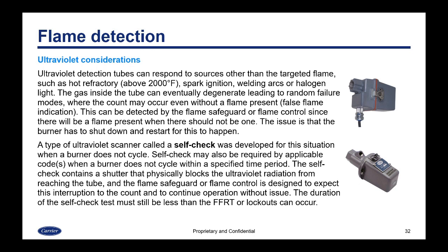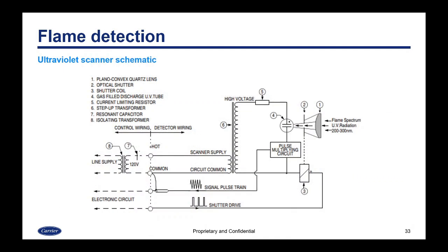A type of ultraviolet scanner called a self-check was developed for situations when a burner does not cycle. Self-check may also be required by applicable codes when a burner does not cycle within a specific time period — 24 hours is a common time period. The self-check contains a shutter that physically blocks the ultraviolet radiation from reaching the tube, and the flame safeguard is designed to expect the interruption to the count and continue operation without issue. The duration of the self-check test must still be less than the flame failure response time or lockouts can occur. Here is a schematic of how an ultraviolet system works, showing the electronics as well as where the flame reaches the bulb — the physical manifestation of sensing the flame.